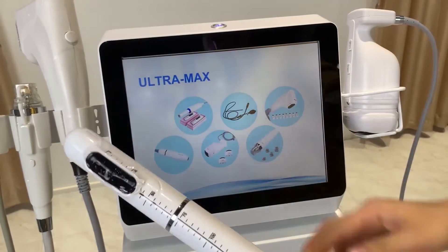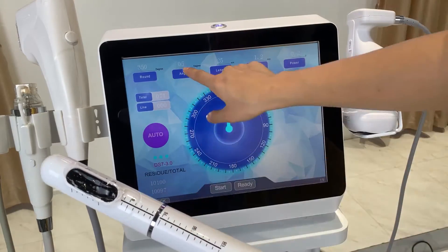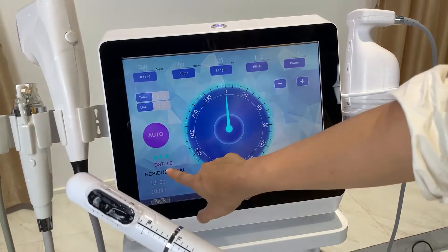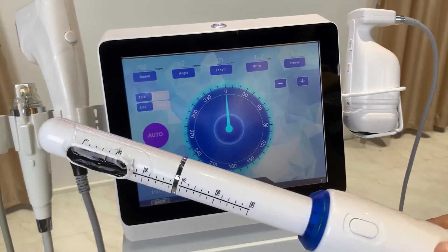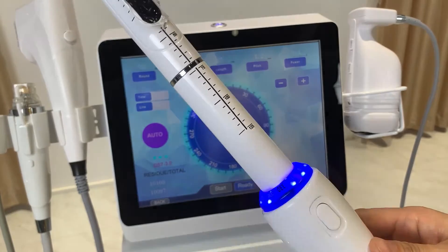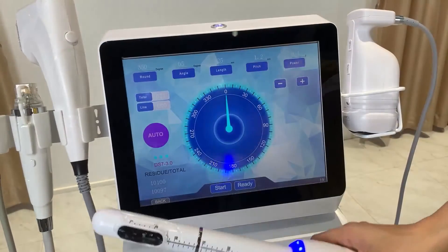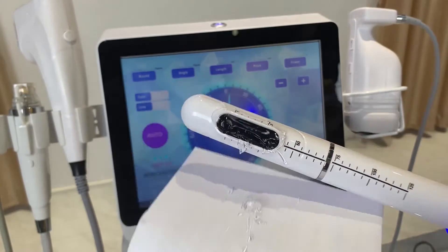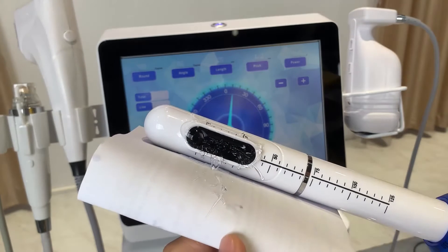Now I'll show the vaginal HIFU handle settings. You set the degree of each turn — for example 5 degrees per turn — and the energy level, which can start from 0.4 joules. This uses a 3mm cartridge. Press the ready button and the handle will perform a 300-degree rotation. After the indicator lights up, press the start button and then the work button to begin energy delivery. After delivering one line, the handle will auto-turn by 5 degrees.